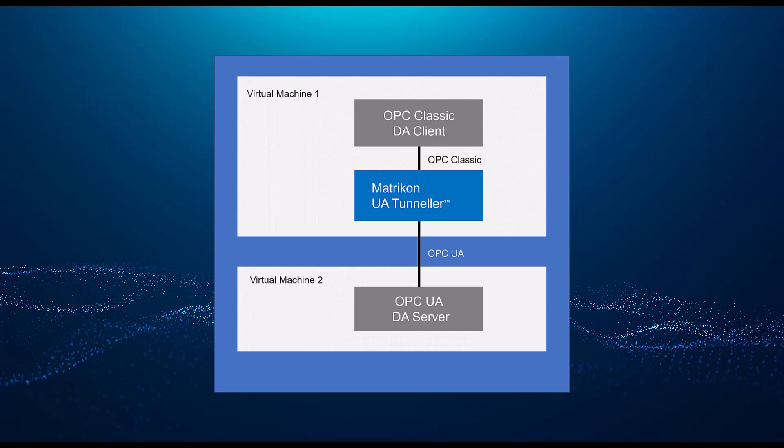Recall that OPC UA, by specification, is firewall friendly. Therefore, we will have the classic OPC DA client connect locally to the Matrikon OPC UA Tunneller. Tunneler will convert the OPC DA to UA and then remote connect to the OPC UA server using a single TCP port.